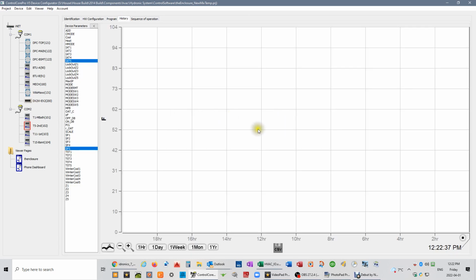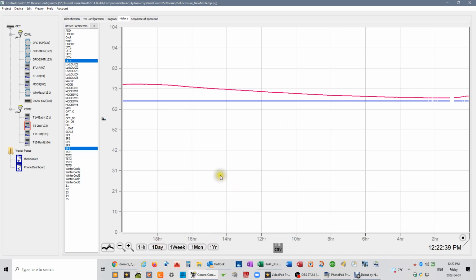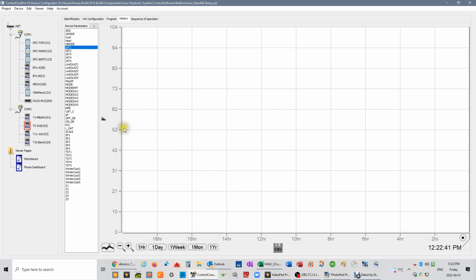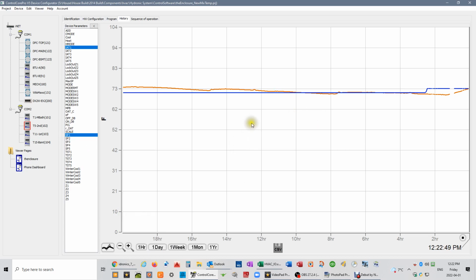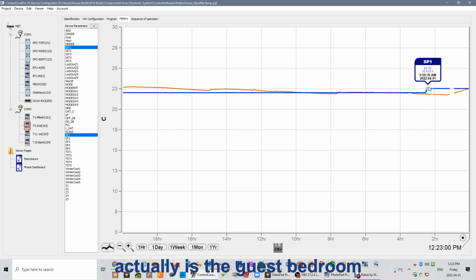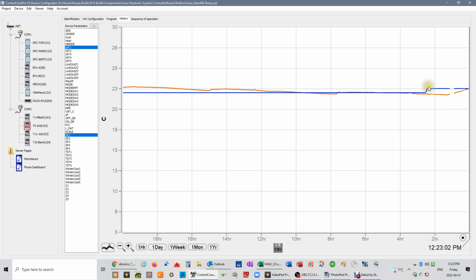So in order to look at that, let's look at a single day. I'm going to look at zone 1. So I have the temperature sensor for zone 1 and I have the set point for zone 1. And you can see that it's hovering just above and below the set point. You can see I boosted it up. This is the main room downstairs, the great room, and it's a cloudy day. So I boosted it up to 22.5 from 22 just to ensure that the system ran.